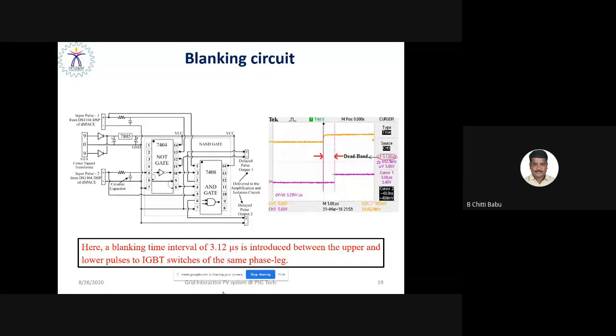So this is very important, but we do not say that this is the accurate time delay it has to ensure. Of course, that depends on the different control and modulation techniques as well. Why? If the dead band is too much, maybe 5 microseconds or maybe 10 microseconds, then you might know there is a non-uniform PWM pulse generation, and again it can cause current distortion, inverter output current distortion. And again it creates the problem of power quality.